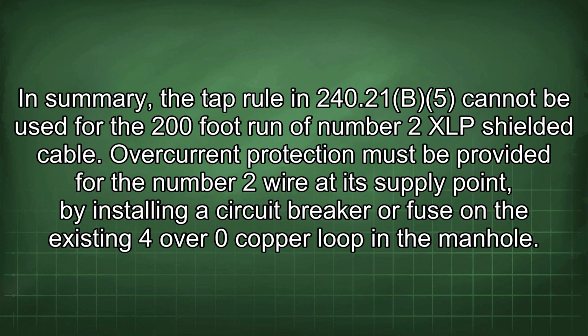In summary, the tap rule in 240.21(B)(5) cannot be used for the 200-foot run of number 2 XLP shielded cable. Overcurrent protection must be provided for the number 2 wire at its supply point by installing a circuit breaker or fuse on the existing 4/0 copper loop in the manhole.